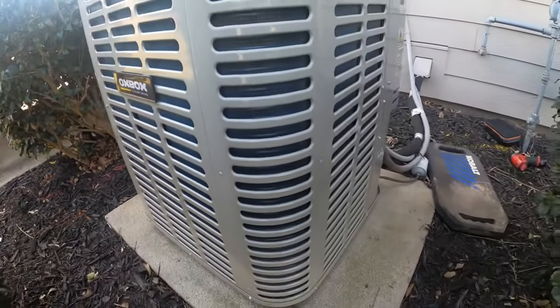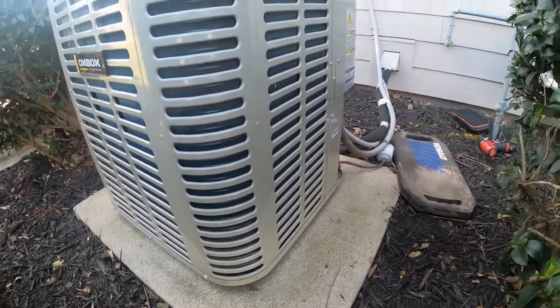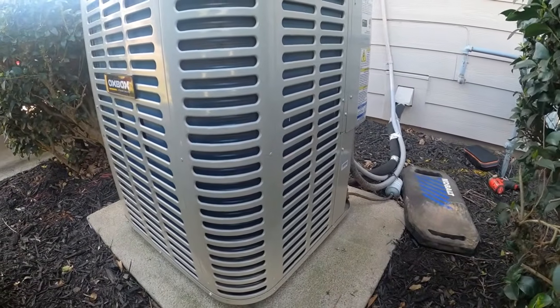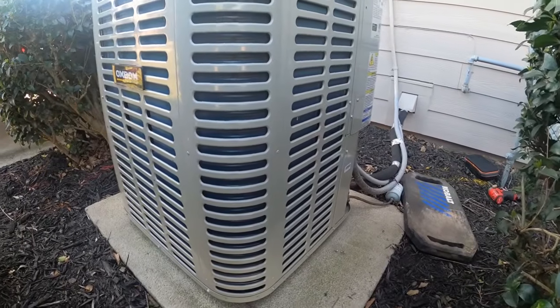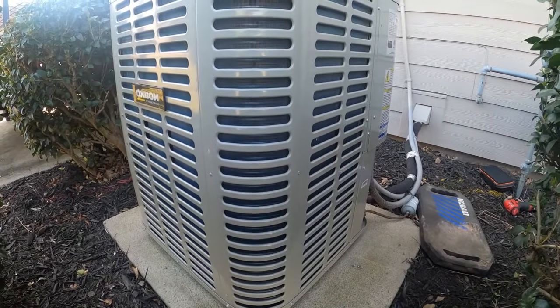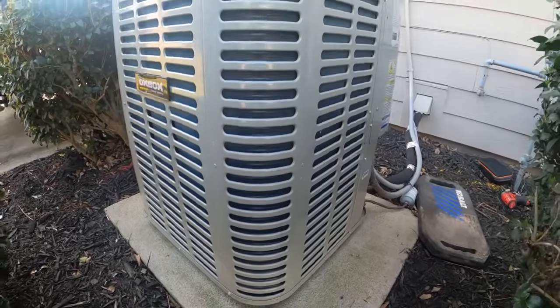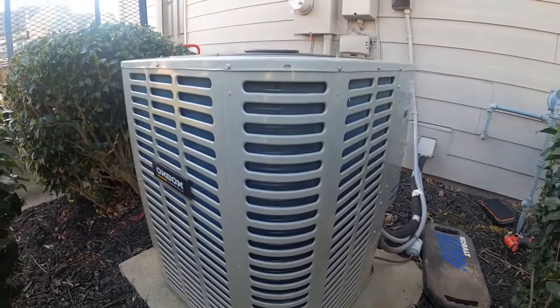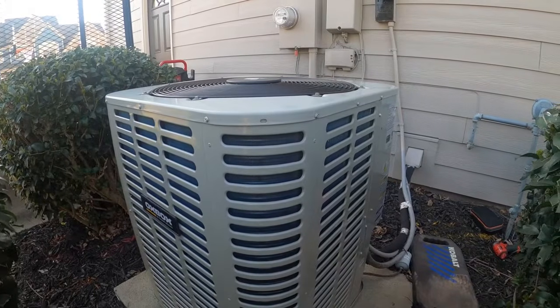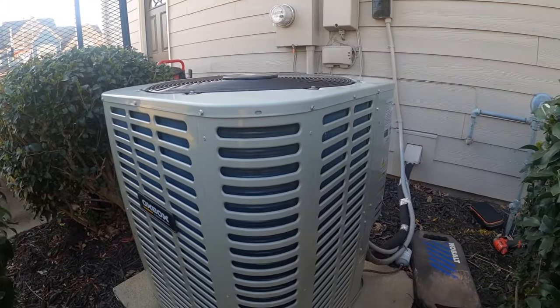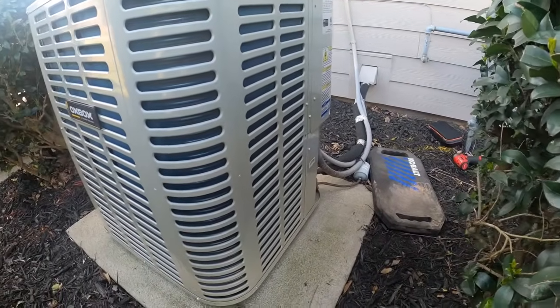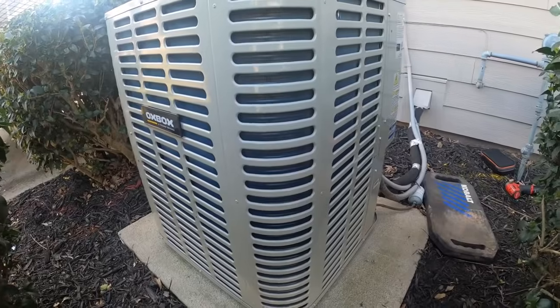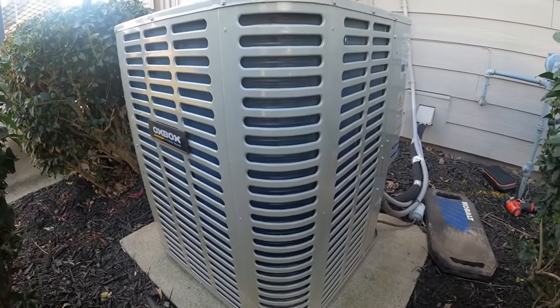But anyway, the reason we're at this house is, well, this system was installed 2 years ago. It was supposed to be a dual fuel system, but whoever installed it set it up as a straight AC with a gas furnace, and we have a heat pump out here. Zone board will not operate, the one that's installed anyway, from what I understand, a dual fuel system. So we've got to put in a new zone board, come out here and put an outdoor temperature sensor so we can set our temperature lockouts for our heat transition from heat pump to gas, compressor lockout.